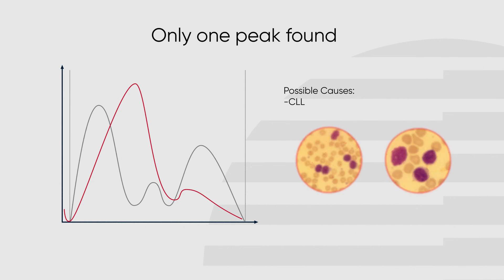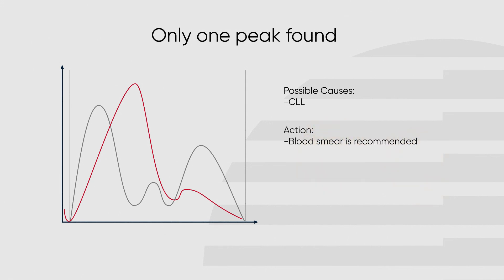Detection of only one peak in the WBC histogram may be caused by chronic lymphocytic leukemia (CLL). Due to the malignancy, the bone marrow focuses on the production of normal and abnormal lymphocytes, causing a decrease in the production of mid cells and granulocytes, noticeable in the histogram as an absence of those peaks. If this occurs, the system may give an OM flag; proceed to confirm the abnormality in smear.